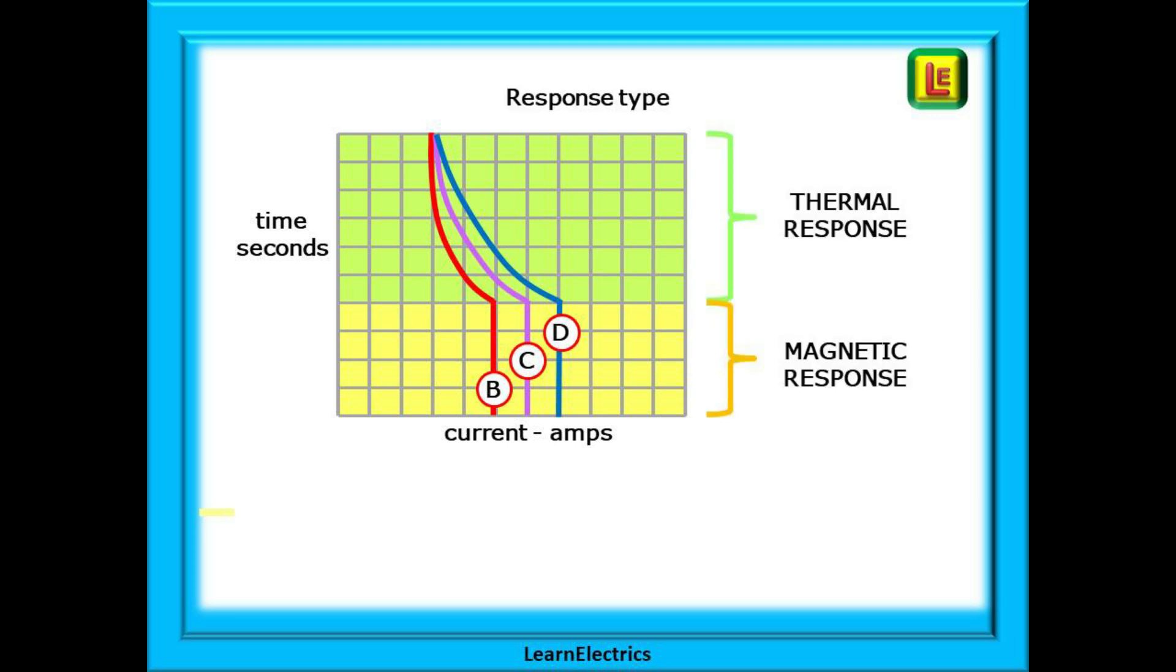So where does the knee fit in? The knee divides the chart into two halves. The upper half is the thermal response part telling you what happens to the bimetallic strip. The lower half below the knee is the magnetic response of the solenoid which is pretty much instant.